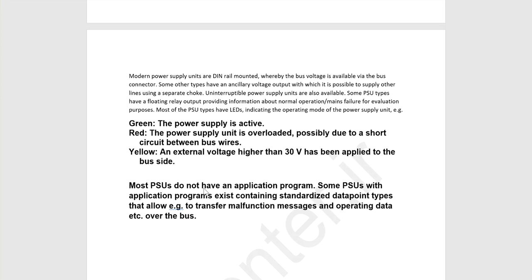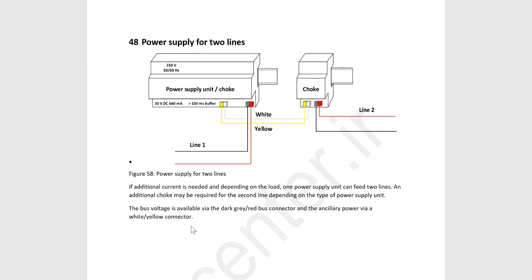Yeah. Most power supply units do not have an application program. Remember that we don't have a physical address or application program. Some power supply units with the application program exist, containing standardized data point types that allow, for example, to transfer malfunction messages and operating data. Okay, so nowadays the power supply unit reports themselves. For example, the power supply says what is the voltage I use and what is my output and how about my temperature and so on. So the power supply transmits their data on a bus. In this case, you should have the physical address and application program, of course.